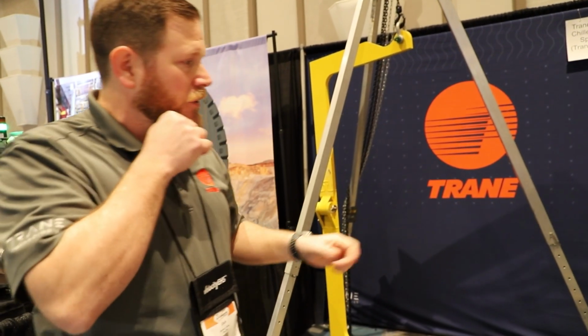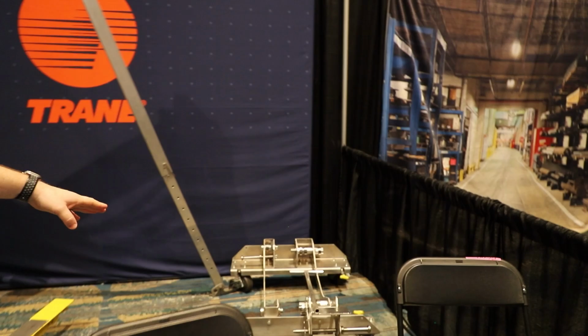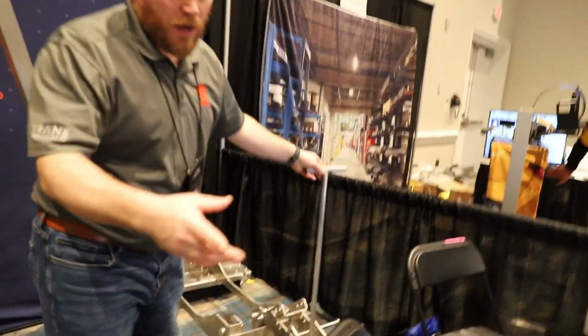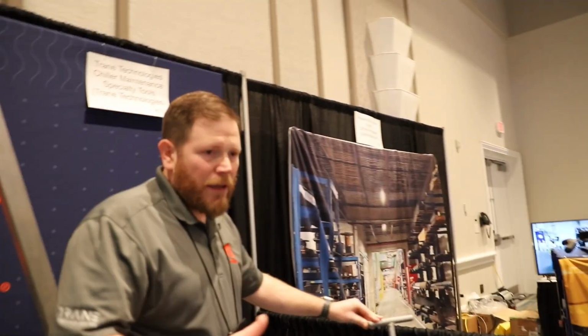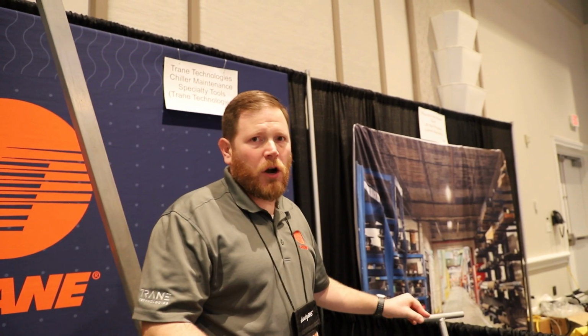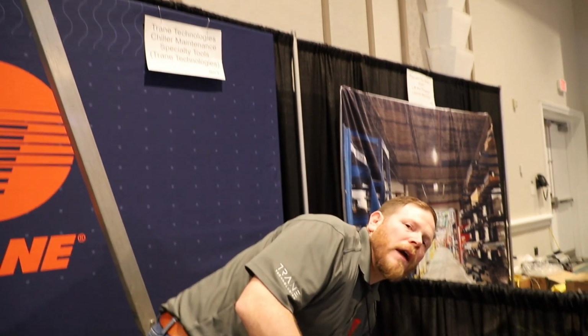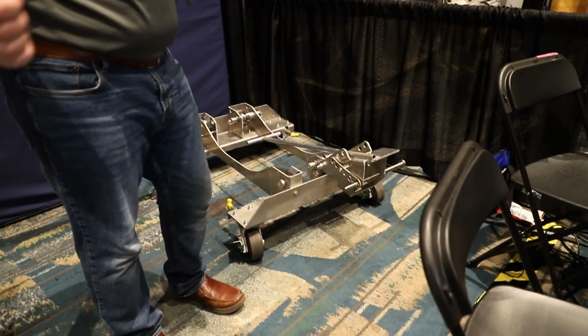So the next tool we have is in the far back corner here—that's our interstage casing cart. After the suction cover comes off our chillers, the next piece to come off is our interstage volutes. The old way of doing the work was technicians would drop the interstage volutes directly to the ground, then roll it around by hand, usually with 2 technicians. The flanges on the volute aren't the same dimension, so it already has a lean to it.